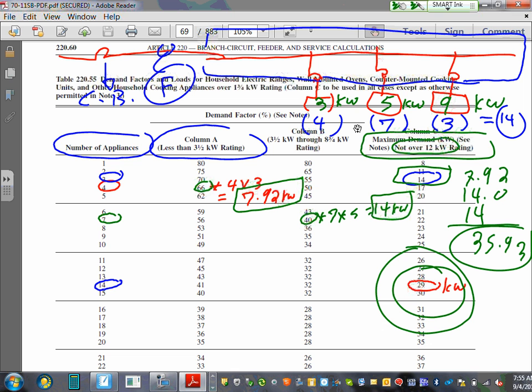Any comments, guys? Any questions about the range? The smallest of the two. Okay, now when we size this service, somebody do me a favor. When you size the conductor, we need to size this conductor, so we came up with 29. So we need to find I. So 29K divided by 240. Why 240? Because the system is 240 volt. So divide this one by 240 and find me the amp, will you?